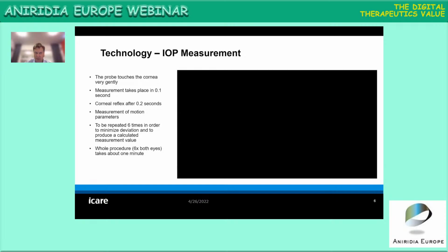About the technology measurement, I will show you soon a video in my presentation, but before that I will explain what happens in the video. The probe in the tonometer touches very gently to the cornea. The measurement takes 0.1 second. The corneal reflex happens after 0.2 seconds. So we can say that one measurement is faster than the human reflex. It measures different motion parameters, and the final result comes from 6 measurements to minimize the deviation and to produce a calculated measurement value. The whole procedure of one measurement is 6 times in both eyes, and the whole measurement process takes about 1 minute. And now I will show you the video.